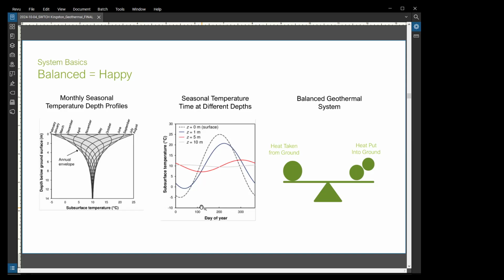Because when you hear about people having issues with geothermal systems, it's mainly because they haven't maintained that balancing over time. So maybe one year you're monitoring the temperature of your loop, the temperature that the water's going in and coming out at, and you see you've lost a couple degrees. Maybe you had an exceptionally warm summer, or an exceptionally cold winter, and those might cause shifts in the temperature on a year-to-year basis.